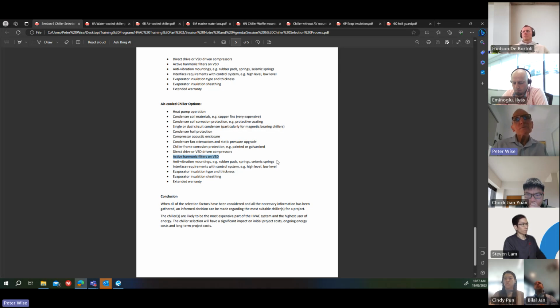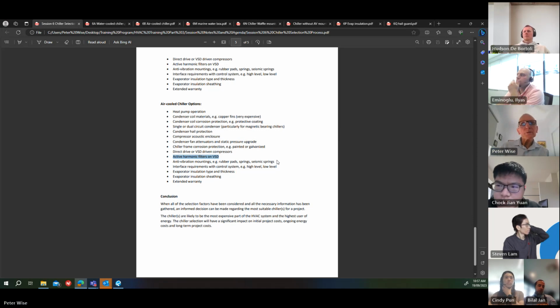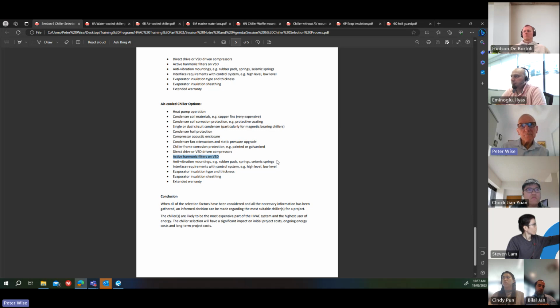The magnetic bearing chillers are extremely well balanced and vibration free. And some people had their doubts about this, but I have experienced it myself. We worked on a project that needed very tight vibration control, but they wanted to use an air-cooled chiller. Their preference was a magnetic bearing chiller, and on this particular project there was actually a noise and vibration consultant, and he said he wanted the chiller on springs.